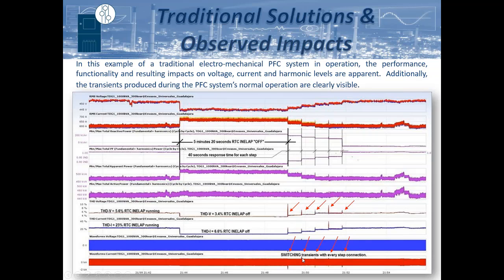Now, these transients are not only applicable at the system, where they can damage the internal components, as was stated by John previously on the poll question. This is quite frequently why traditional power factor correction systems are in constant need of maintenance, because these transients are going to propagate not only within the system, but also on the entire network, and can actually have an impact on systems and processes further downstream.